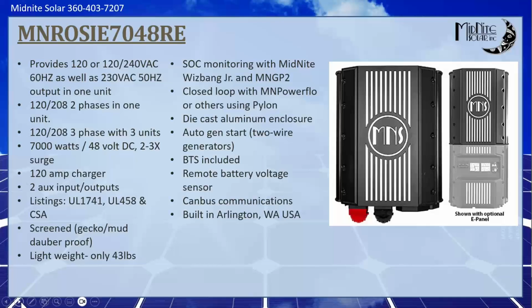The Rosies have a couple auxiliary input-outputs that you can use to drive things like automatic generator start, a diversion load, a vent fan, et cetera. Just a lot of functionality there. 120 amp charger. So at full boogie, the Rosie will charge at about 120 amps DC. Some generators, if the generator is not real clean, will be a little less than that, but it'll be close to that. And you can stack Rosies in parallel.